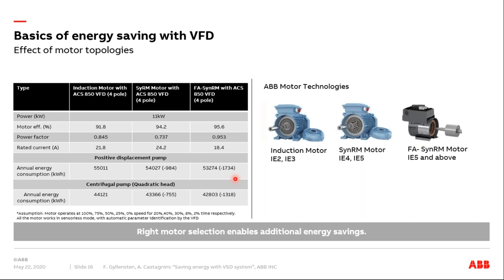But in general, in 4 to 5 years, you should be able to get a payback for using a more efficient motor in this system. The same is true with the centrifugal system. With centrifugal pumps, you would reduce the amount of energy used for the same system and the same load cycle by using a more efficient motor, even with a VFD, and it will give you a payback period of 4 to 5 years.